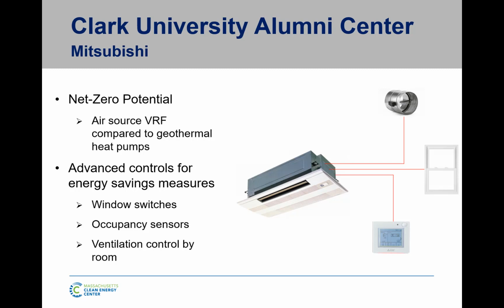Thermostat on this unit, built-in occupancy sensor. So this is what's telling that damper whether or not it should be open and whether or not the unit should run. You leave the room, 10 minutes later the unit's being set back because it's not occupied, and it's not being turned back on until someone walks in the room. So the ability to handle a change in schedule and get that savings from not ventilating the room, not cooling or heating the room when it doesn't need to be.